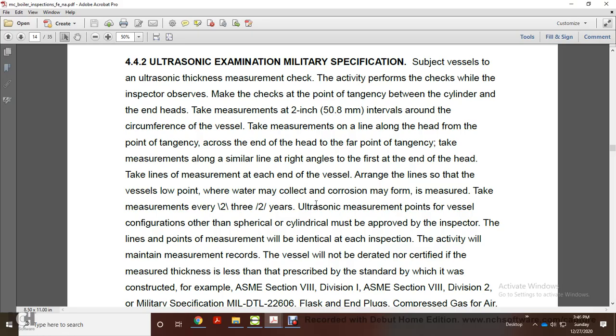Arrange the lines on the vessel below the point where water may collect, where corrosion may form, and measure there. Take measurements every 2-3 years, or 2 years.